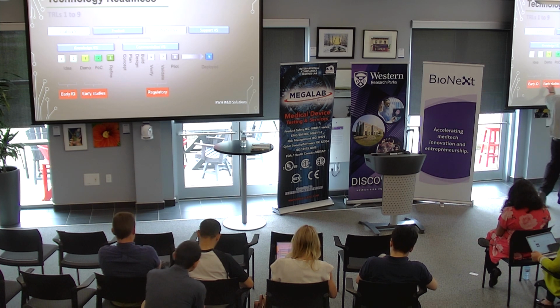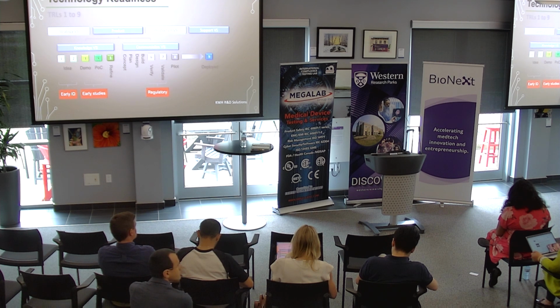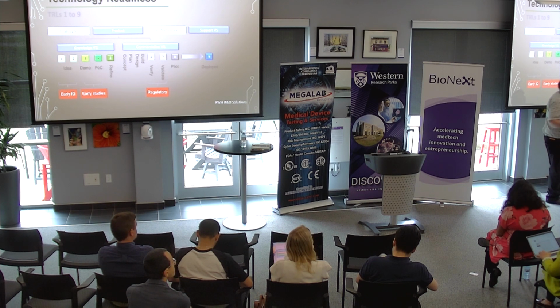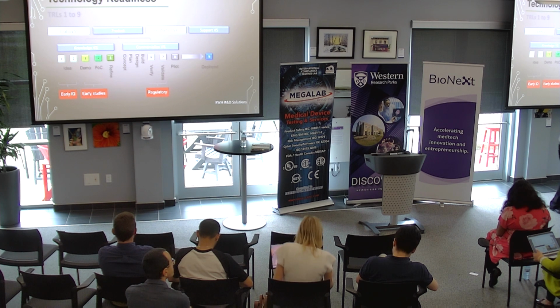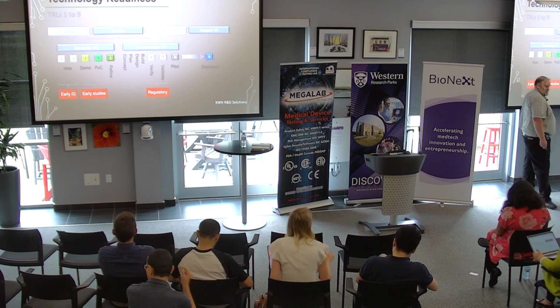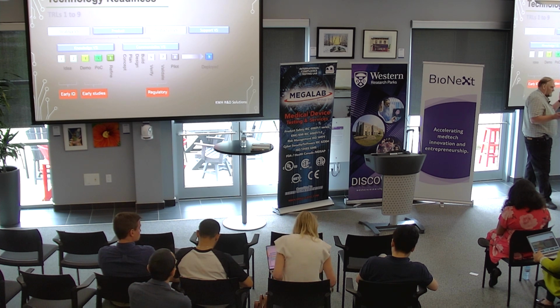So all of this red area is where we can help you from a regulatory standpoint, and where we should get involved. Too many times people get to the pilot phase and then want to get their regulatory affairs taken care of, but by then it's too late. We can help, but any redesign at that point costs more, like Dave was saying - the later in the phase you go, the more redesign you'll have to do, especially if you're not passing tests. If you understand earlier what your design needs to be from a regulatory standpoint, you won't have to spend as much time on bad components or making sure your critical components list is correct.